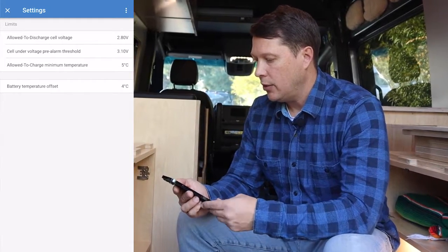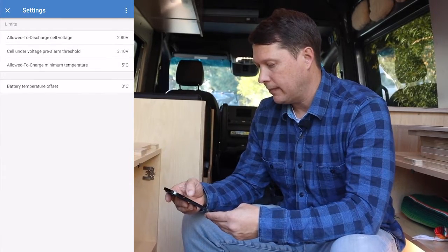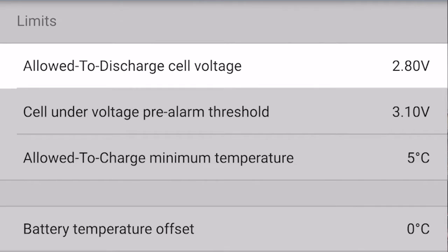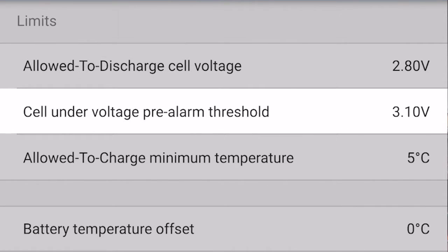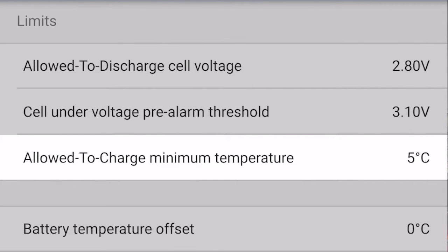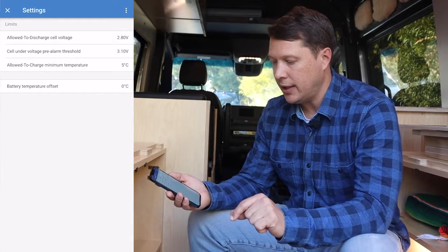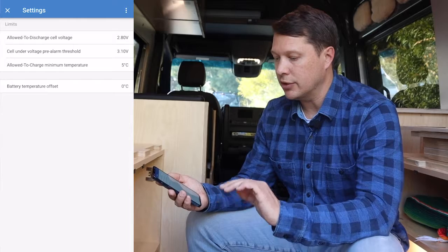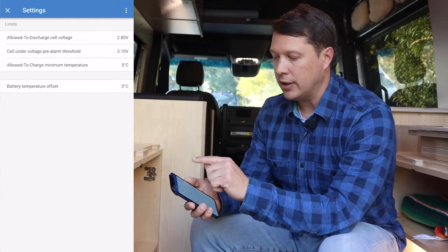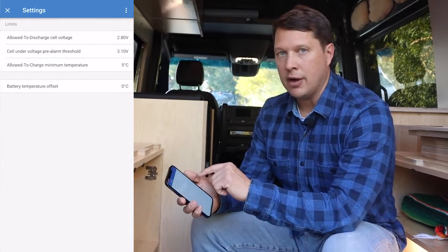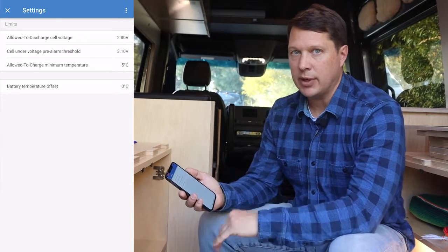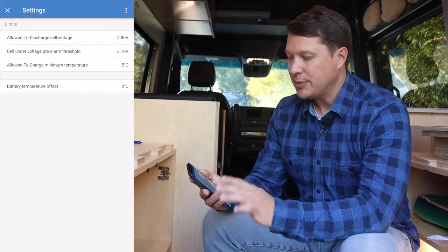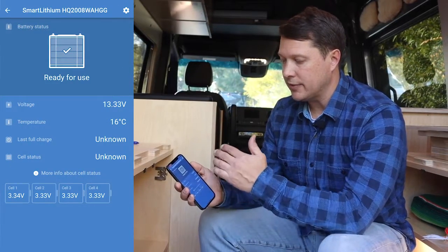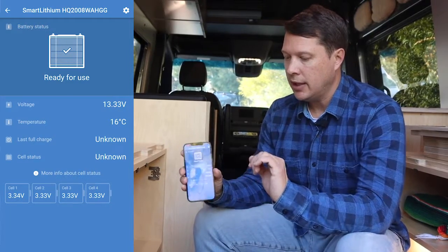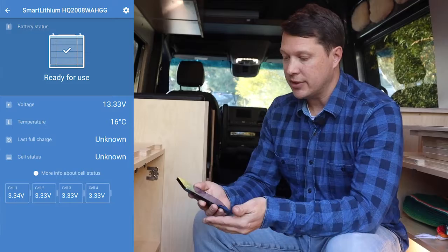Back to the battery settings - we actually leave these at factory defaults, which you can restore. That means the allowed discharge voltage is 2.8, the cell under voltage is 3.1, and the allowed charge minimum temperature is 5 degrees Celsius, about 41 degrees Fahrenheit. At that temperature, the batteries will no longer charge, and if you needed to charge them deeper than that, you could go in and change that setting. There's also a battery temperature offset - if you know the battery temperature differs from what's reading here, you can make that adjustment. But that's pretty much it with the batteries. If you need to find out about voltage, temperature, or individual cell voltages, you can look at the app, but otherwise there's nothing else to change.